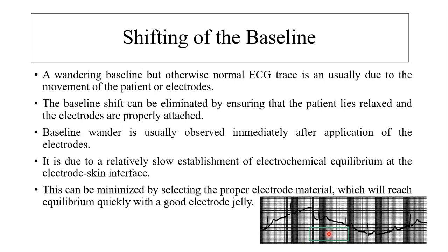Immediately after the application of the electrodes, this error may come, and after the patient stabilizes with the electrodes, it may be overcome. This can be minimized by selecting the proper electrode material and gel, which will reach equilibrium quickly, with a good electrode jelly.